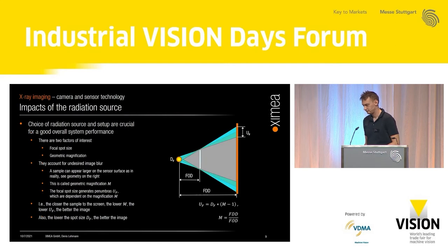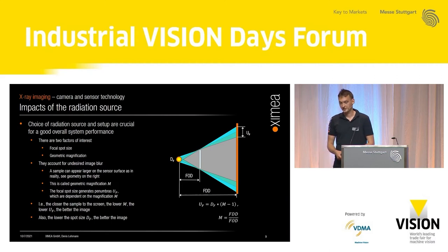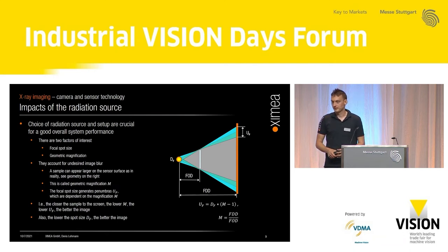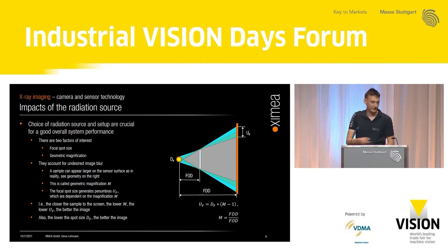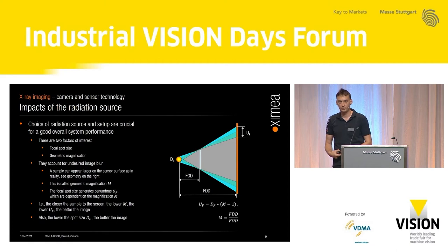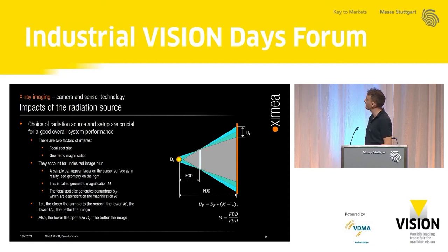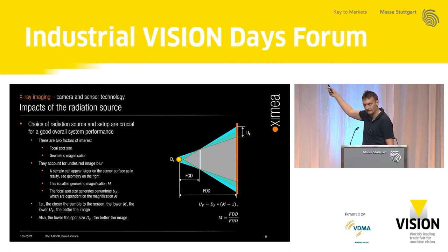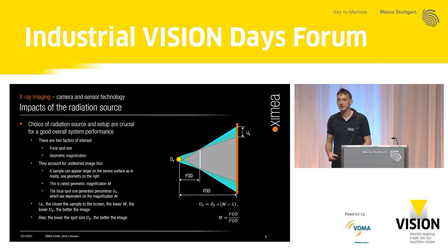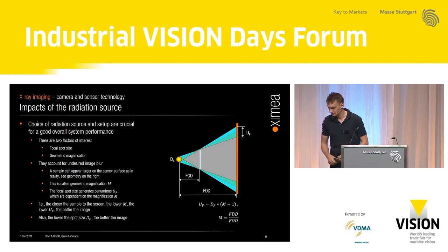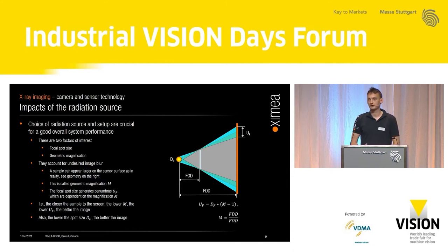Let's start with the radiation source. It has two factors of interest: the focus spot size and the geometric magnification — both of which account for undesired image blur. The closer you move your object to the screen, the less blur you have, because the lower the magnification, the lower the blur effect, as shown in the formula. Also, if the spot size is smaller, the blur effect becomes smaller. In a nutshell: the smaller the spot size and the closer your object to the screen, the better your image.